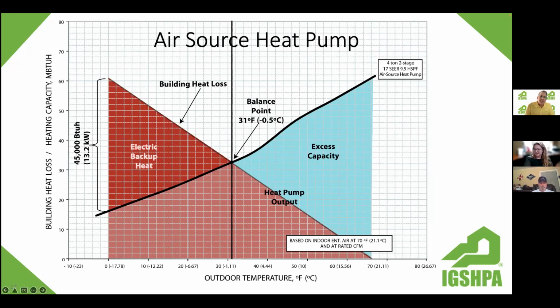So I took the heat pump capacity and subtracted that from the total heat loss, and that's where this triangle comes in right here, the backup electric heat. It's about 45,000 BTUs per hour. If we convert that to kilowatts, we need 13.2 kilowatts to heat the house at 0. Now, of course, we don't need as much when it's warmer outside, but we have to design for our outside temperature that is the design point for that particular location. So I mention this because this affects cost, and this could be some of the hidden costs with electrical requirements, wiring, labor, and so forth.